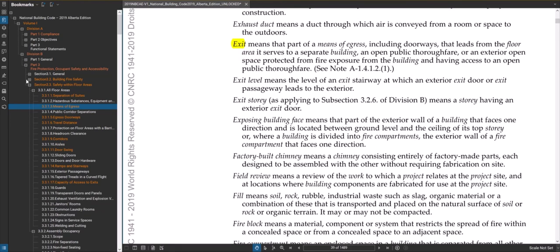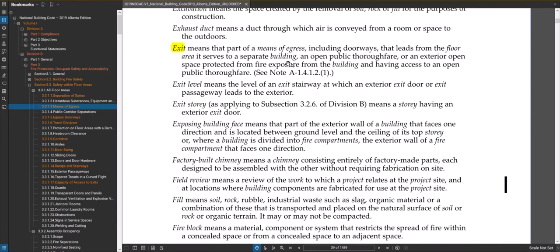An exit is that part of a means of egress, including doorways, that leads from the floor area it serves to a separate building, an open public thoroughfare, or an exterior open space. For example, if you have a second floor with a stair, that exit stair would be a protected, fire-rated zone leading out to the public thoroughfare. It's still part of the overall path of travel — the means of egress.